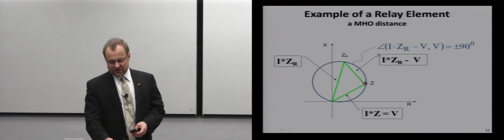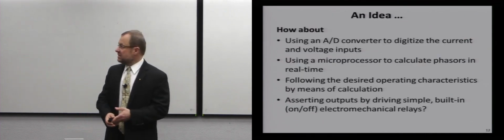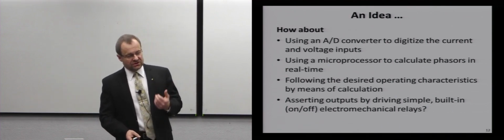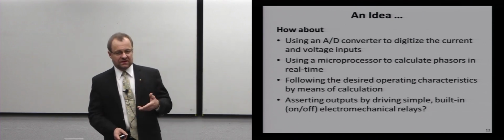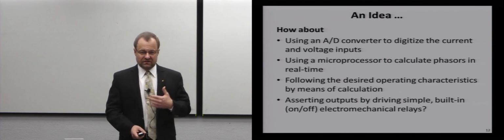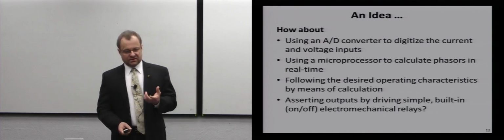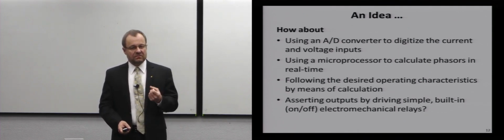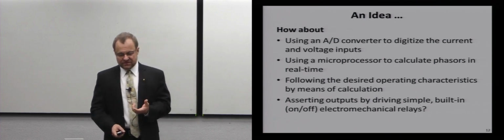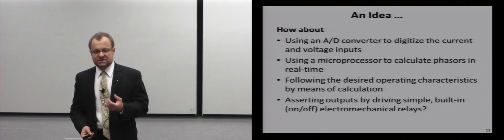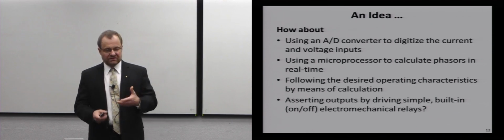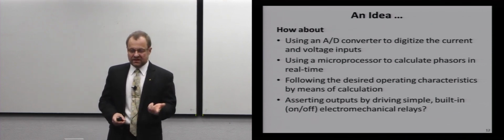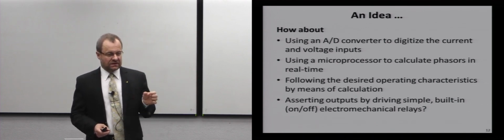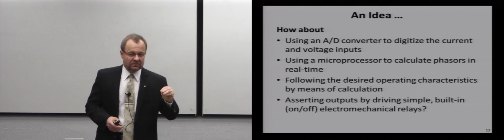So just running this equation in real time, I could build a distance relay, right? So now, an idea. How about using an analog to digital converter to digitize my current and voltage, sample it to the tune of 16, 32 samples per power system cycle, every millisecond or every fraction of a millisecond, use a microprocessor to calculate the phasor, the complex number that represents my current and voltage, then use the same microprocessor to just follow my operating principle, such as do the IZ minus V versus V angle check, whatever calculations constitute my operating equation, and then from a microprocessor assert a signal to a little electromechanical relay, a very generic relay sitting inside the same box, to close the output and allow the breaker to trip, right?